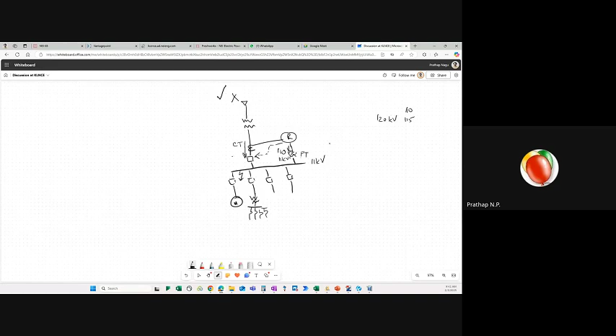And that is why it is very common to see DC systems in substations. All these IEDs are actually powered by a separate battery, right? Plus minus, you send that. Common that I have seen in the US is 24 volt DC, 48 volt DC, and 80% of my projects are always 125 volt DC. I've also seen 250 volt DC, but this is where it's common.